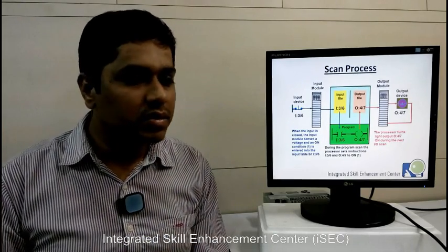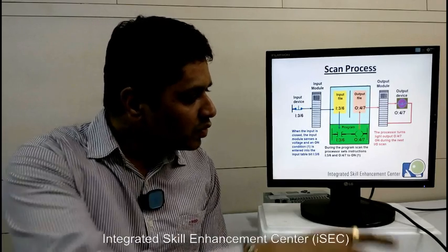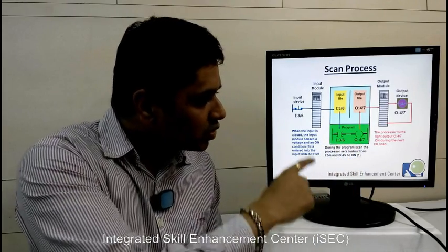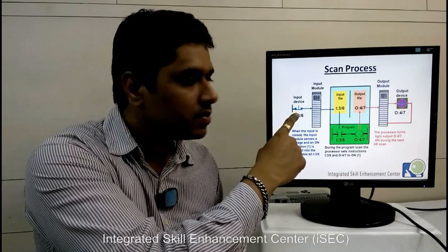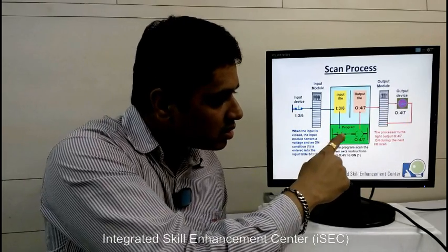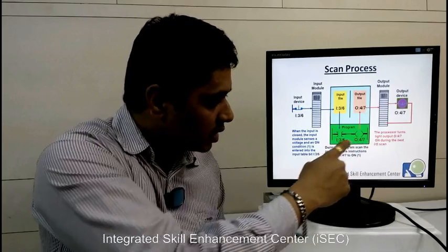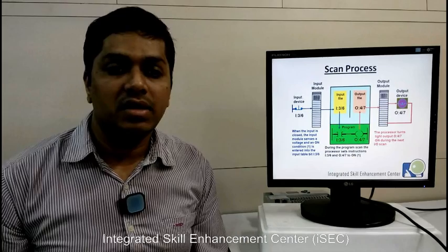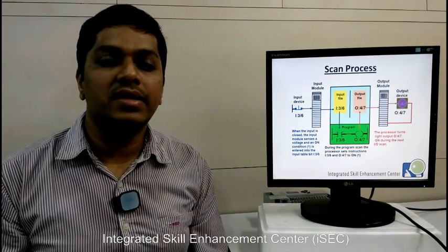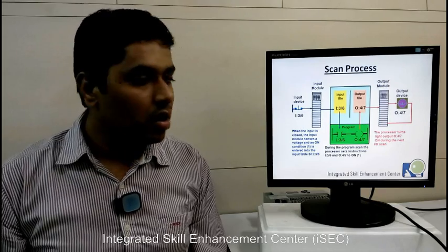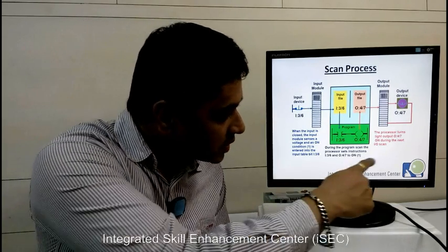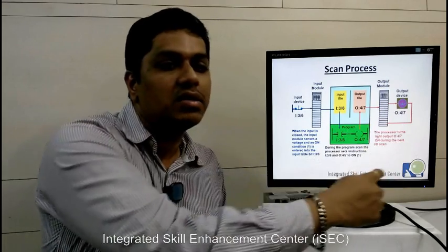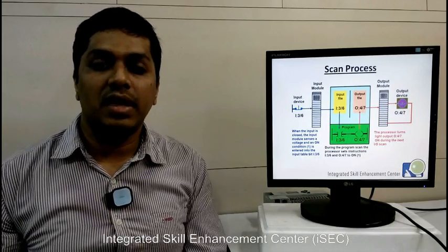This same logic is written here as ladder logic — this is a NO contact and this is an output. So once it is written that when the switch is pressed you have to turn on the bulb, when the input is closed the input module sends a voltage and a condition 1 is entered into the input table. During the scan cycle the program executes the task as per the written program, and in the next scan cycle it turns on the output device, which is the bulb.